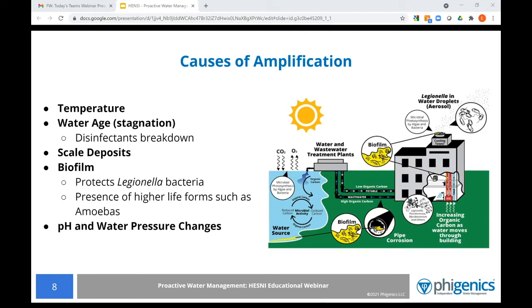So what causes these pathogens to amplify after entering a building? There are a lot of different internal and external factors, and on the screen are the primary internal factors to your facility. A big one is temperature, because the ideal range for amplification is around 95 to 115 Fahrenheit, and that's where most domestic hot water systems operate. So that just puts an added risk to that system. Water age or any stagnation in the piping is another concern because it allows the disinfectants to break down or be consumed. Both scale deposits and biofilm can protect Legionella and other bacteria. Biofilm is especially concerning because it allows for the presence of higher life forms such as amoebas, and Legionella use amoeba to multiply within a water system. And then lastly, any pH or water pressure changes can also contribute to amplification.